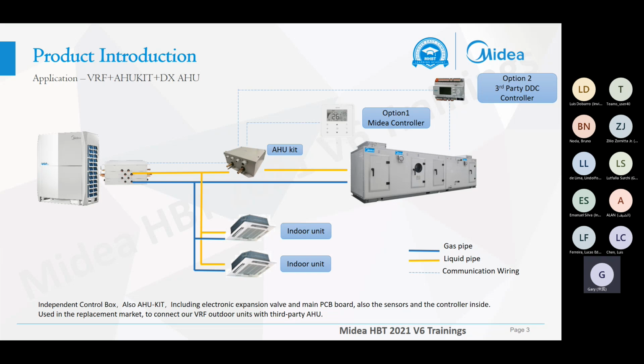As you know, normally we can use our VRF outdoor unit to connect to the standard indoor unit. But the AHU normally connects to the chiller. But we have a special AHU we call the DX AHU. This means the direct expansion AHU. This kind of AHU can connect to the VRF via the AHU kit. This is a simple picture to show the diagram.